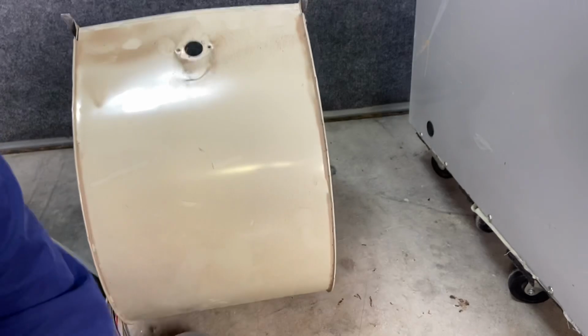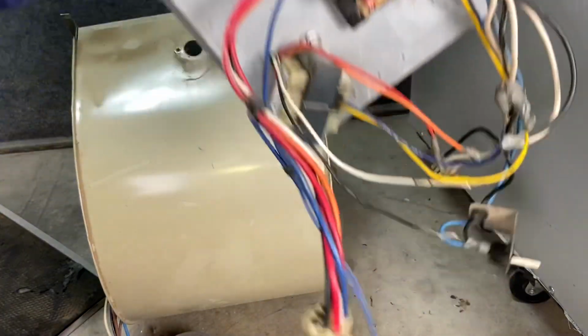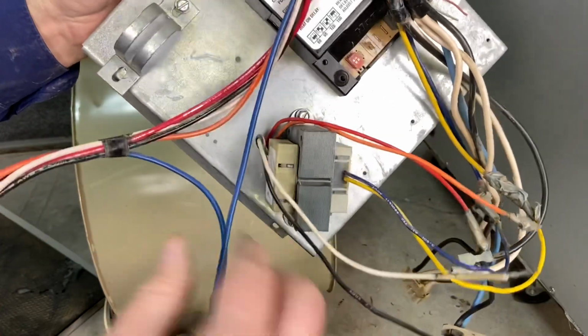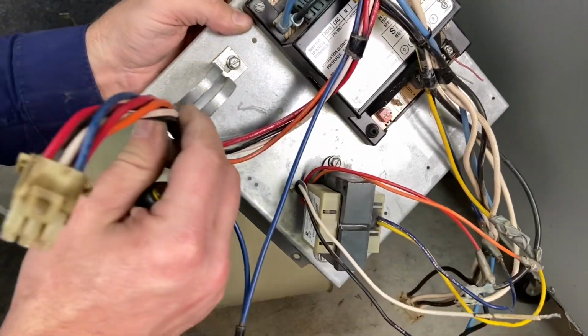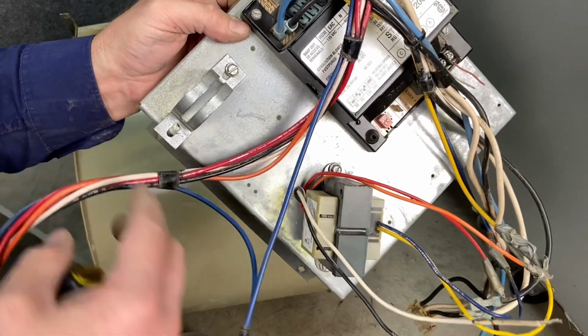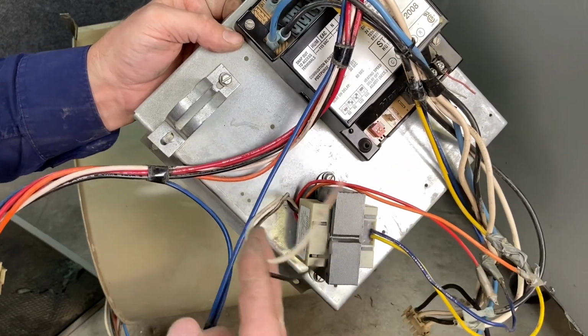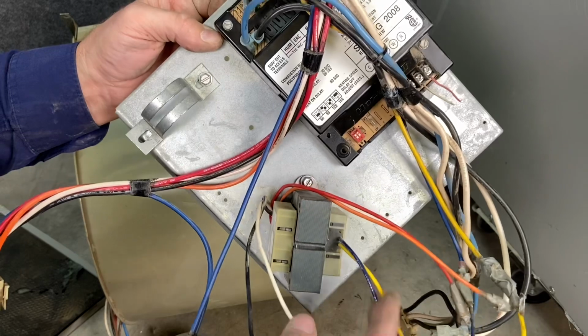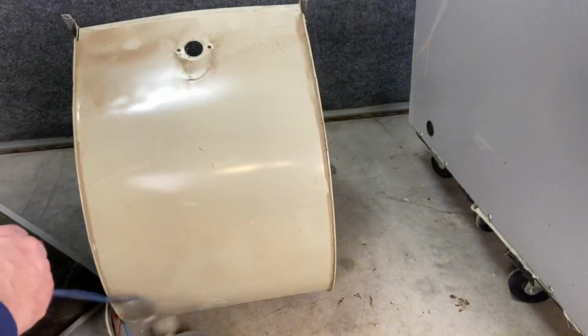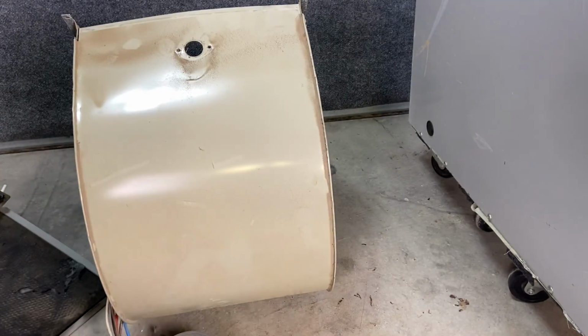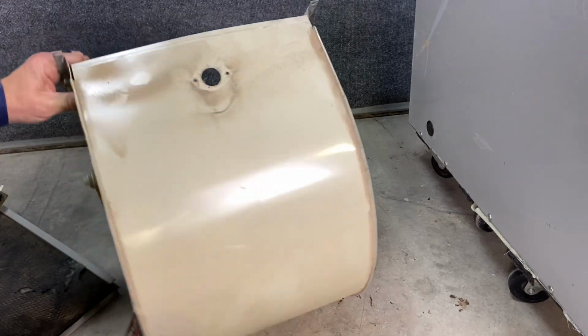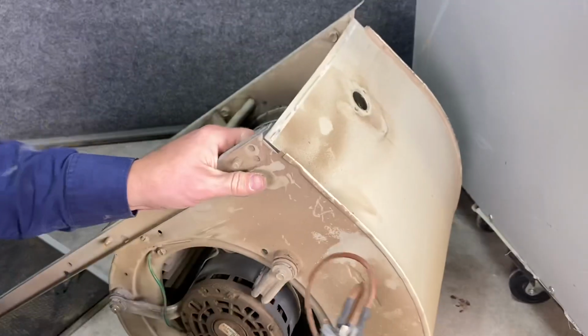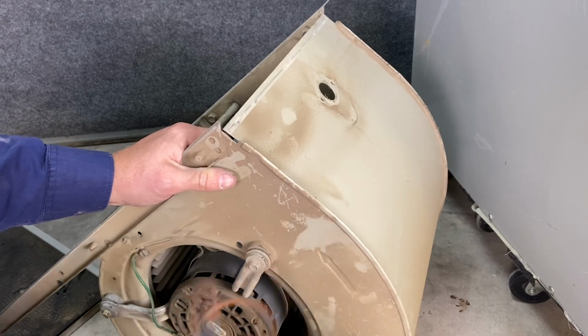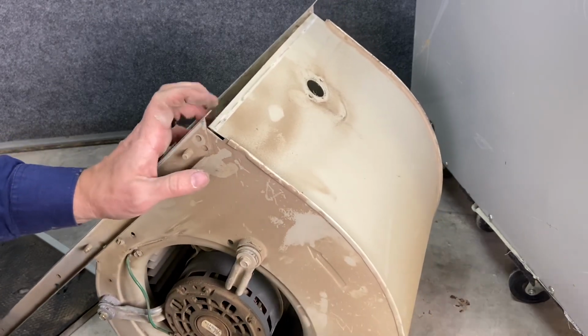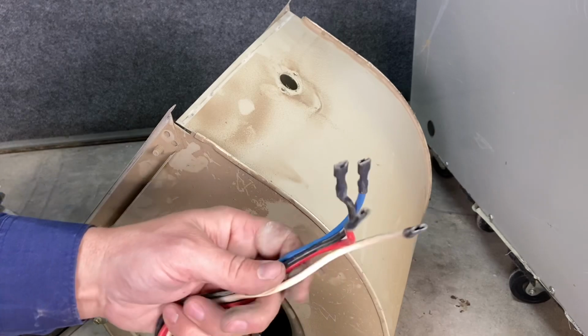So now we have all of our control board wiring separate, and everything's 2 wires, 2 wires, 2 wires, 2 wires to the limit. We have 2 wires to the inducer fan motor and back. We have 2 wires for our main power coming in, 2 wires to the primary of our transformer, 2 wires on the secondary of our transformer. Everything is 2 wires. Even our blower motor, which doesn't look like 2 wires, is still essentially 2 wires at a time. We have the 2 brown wires going to our capacitor, and between our speeds it's going to be any 2 wires at a time.